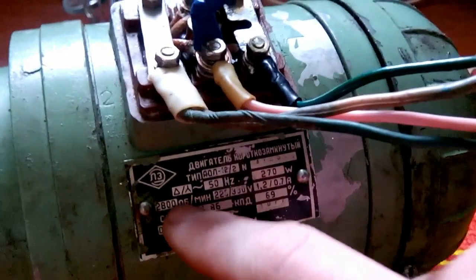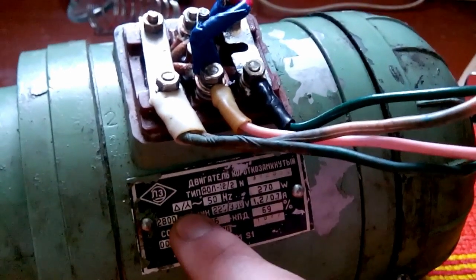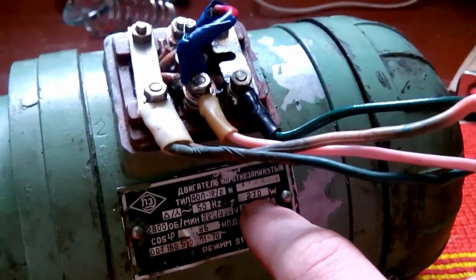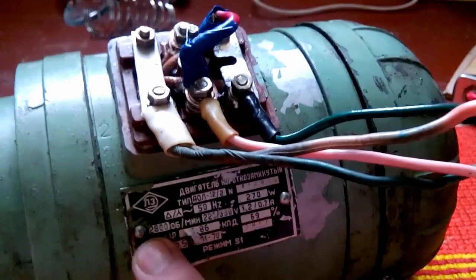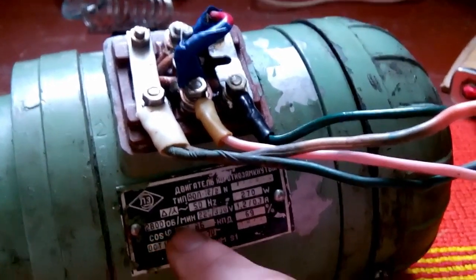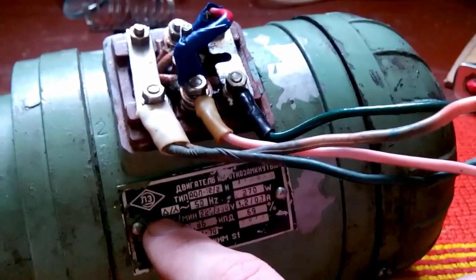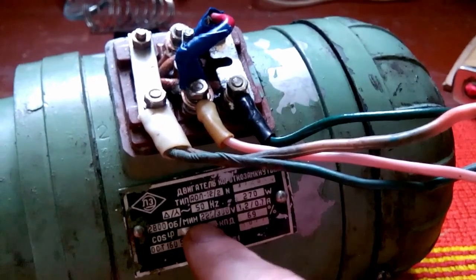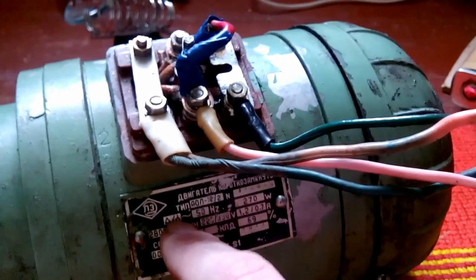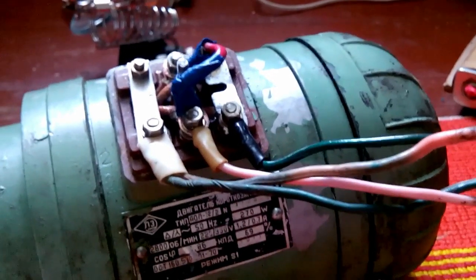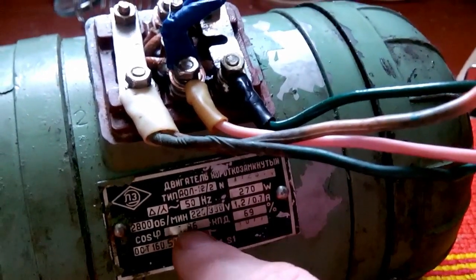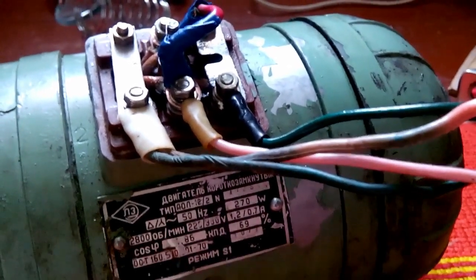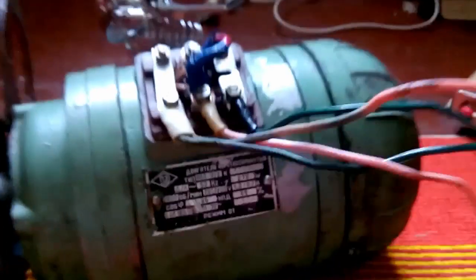You can see the type and numbers. On this label it states that it can be connected in triangle and Y configuration to a 50 hertz supply. It has a power of 270 watts, rotation speed of 2800 RPMs. For triangle configuration it should be 220 volts 50 hertz supply; for Y configuration, 380 volts 50 hertz. It consumes 1.2 amps in triangle configuration and 0.7 amps in star configuration. It has a power factor of 0.86, which is not that shabby considering it's an inductive load, and efficiency of 69 percent.